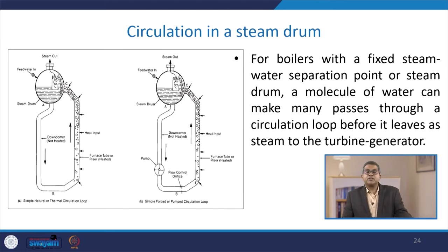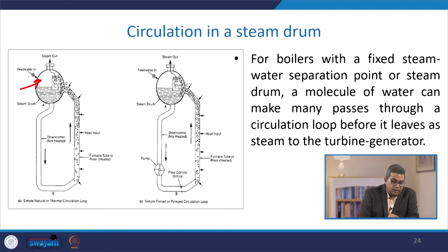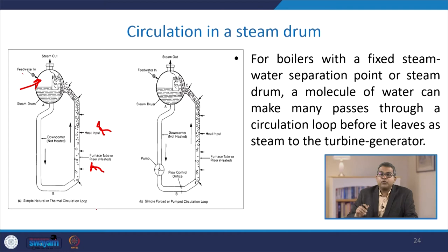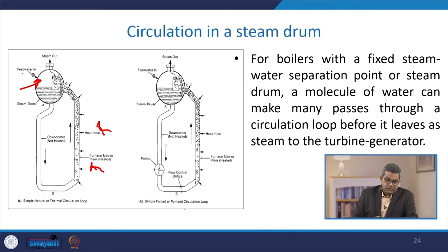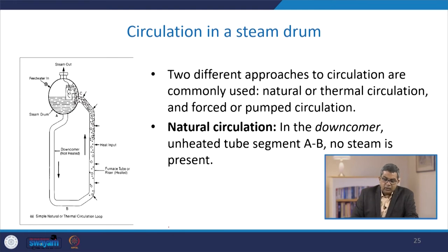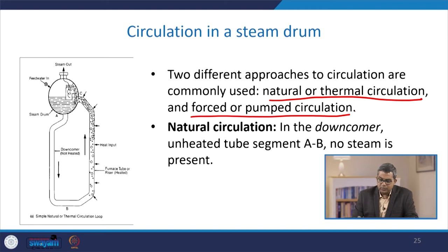Now let us talk about circulation in the steam drum. In this system, steam comes out at the top, feedwater enters, and heat input is provided below via risers — this is simple natural circulation. For boilers with a fixed steam-water separation point or steam drum, a molecule of water can make many passes through a circulation loop before it leaves as steam to the turbine generator. Two approaches for circulation are natural or thermal circulation, and forced or pump circulation.